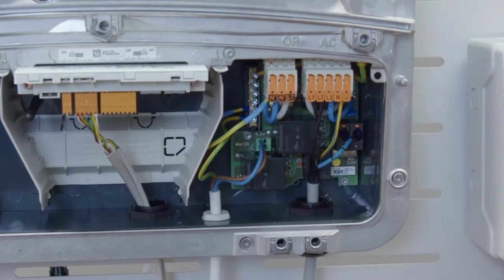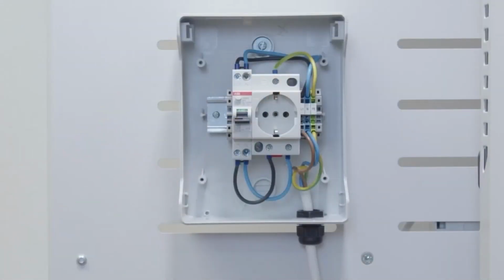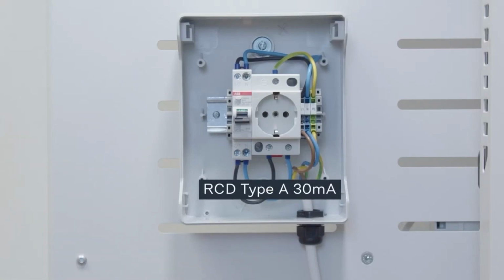After we finish the installation of the AC side and the PV point side, we can then close the cover of the Gen24 Plus again. For the connection to the socket or to the single phase outlet that you want to install on the PV point comfort, please make sure that you have at least an RCD type A 30 milliamps as well as a circuit breaker with 13 amps to secure your electrical line. You can do that like we did, for example, with a combined device of an RCD and a circuit breaker in one, with a 13 amp circuit breaker and a 30 milliamp type A RCD.